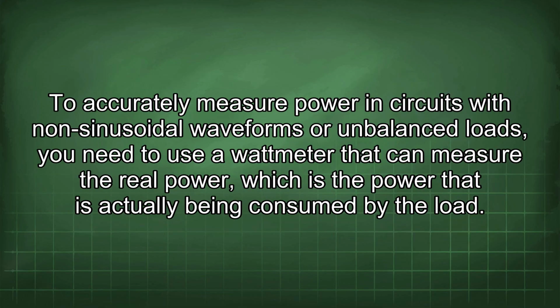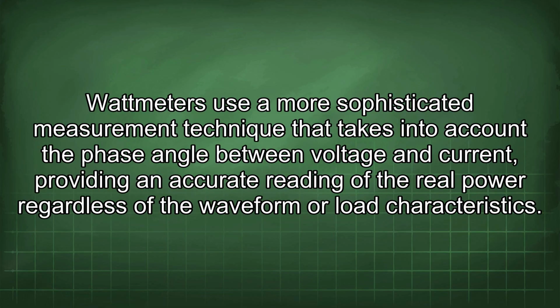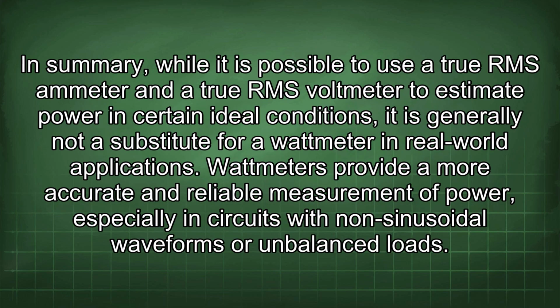To accurately measure power in circuits with non-sinusoidal waveforms or unbalanced loads, you need to use a wattmeter that can measure the real power, which is the power that is actually being consumed by the load. Wattmeters use a more sophisticated measurement technique that takes into account the phase angle between voltage and current, providing an accurate reading of the real power regardless of the waveform or load characteristics. In summary, while it is possible to use a true RMS ammeter and a true RMS voltmeter to estimate power in certain ideal conditions, it is generally not a substitute for a wattmeter in real-world applications. Wattmeters provide a more accurate and reliable measurement of power, especially in circuits with non-sinusoidal waveforms or unbalanced loads.